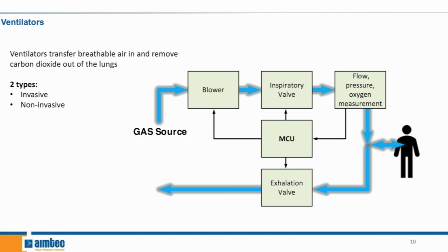The blower pushes air from the gas source, which can just be oxygen or a mix of oxygen and other elements, through the inspiratory valve and multiple sensors and eventually into the patient's lungs. At the same time, the MCU monitors the readings from the sensors and controls the blower speed or valve opening to achieve the desired pressure, flow rate, and oxygen levels.